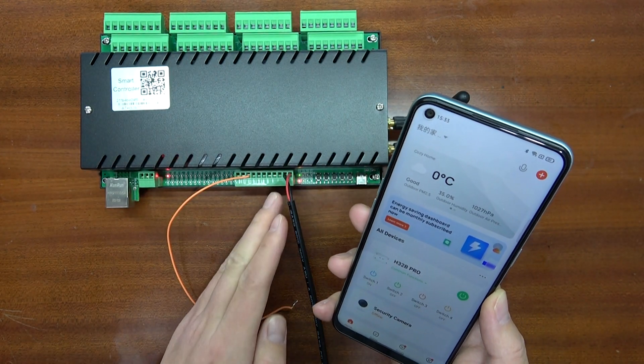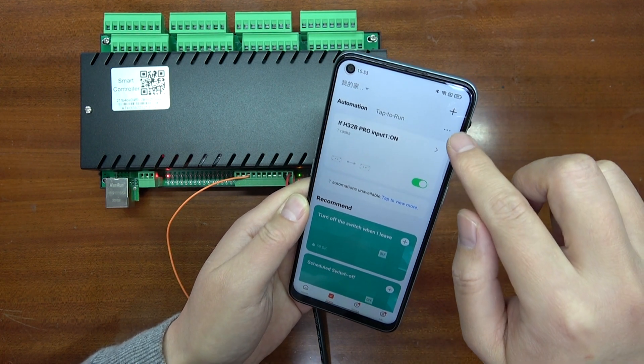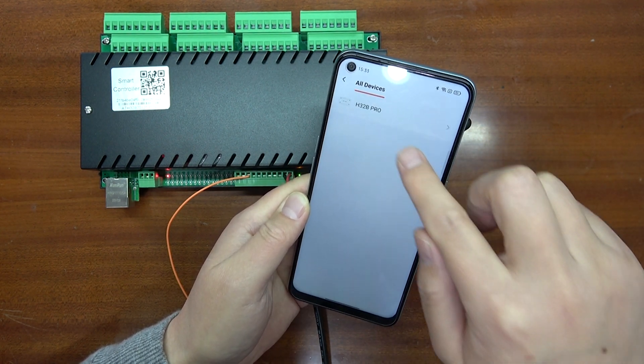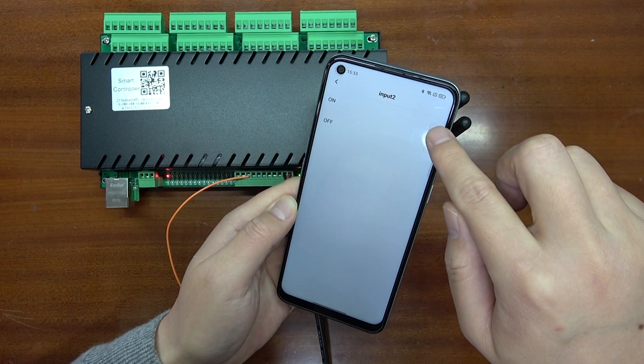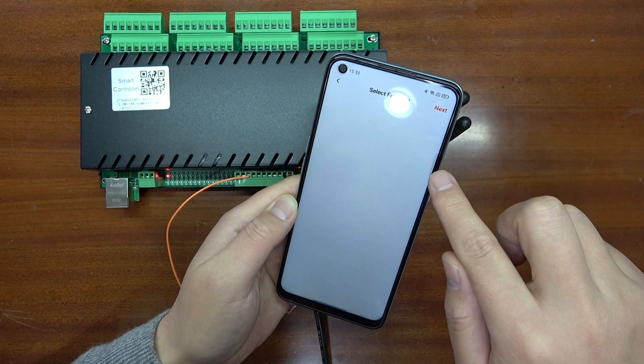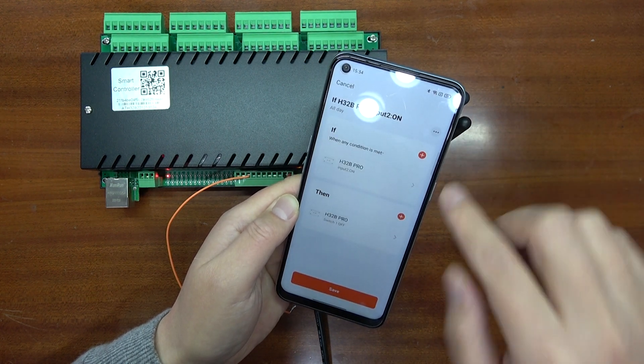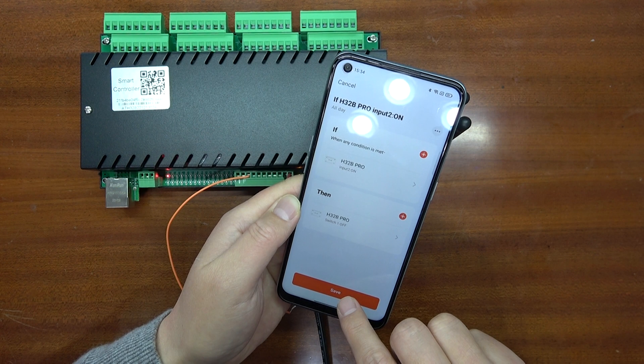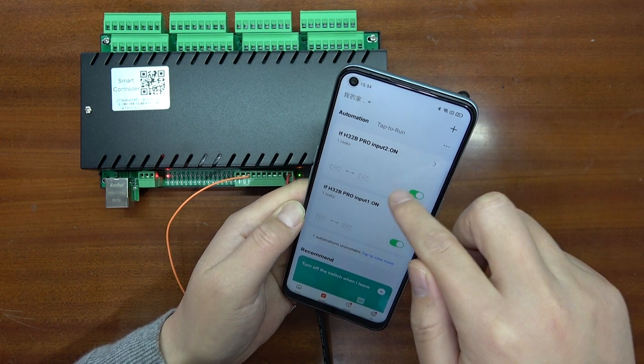If you want channel 2 digital input to turn relay 1 off, you can create another scene for automation. Set the condition: H32B PRO input 2 becomes on, then run the device — H32B PRO relay 1, switch 1, set to off. Save, then you can also add more relay actions such as relay 2 off and relay 3 toggle. Press save and enable it. Now we have created this new automation task.